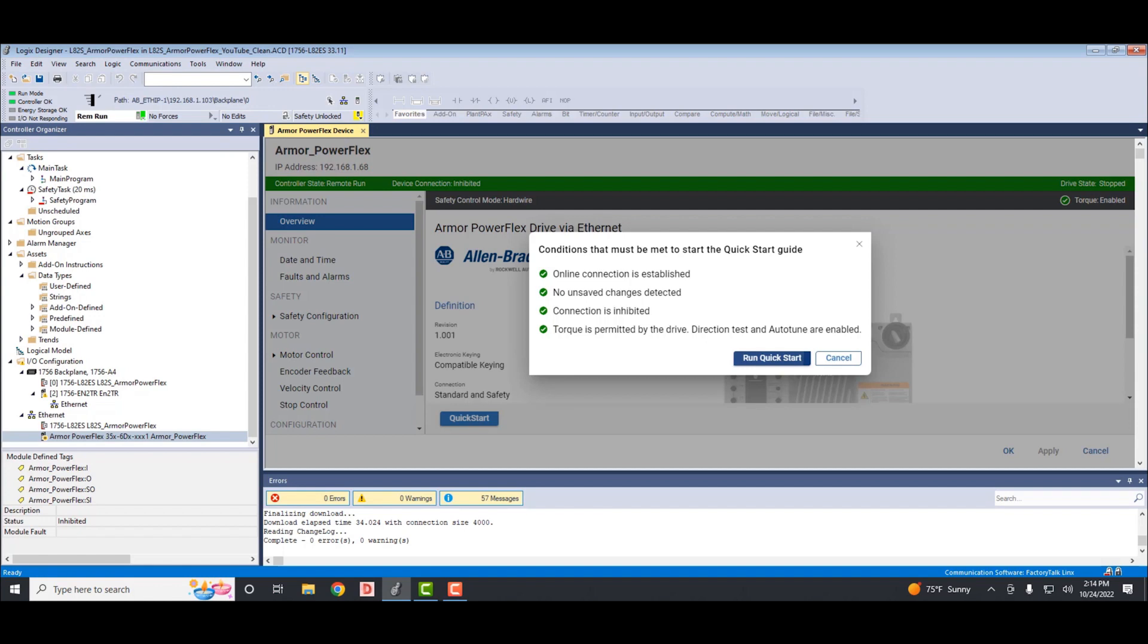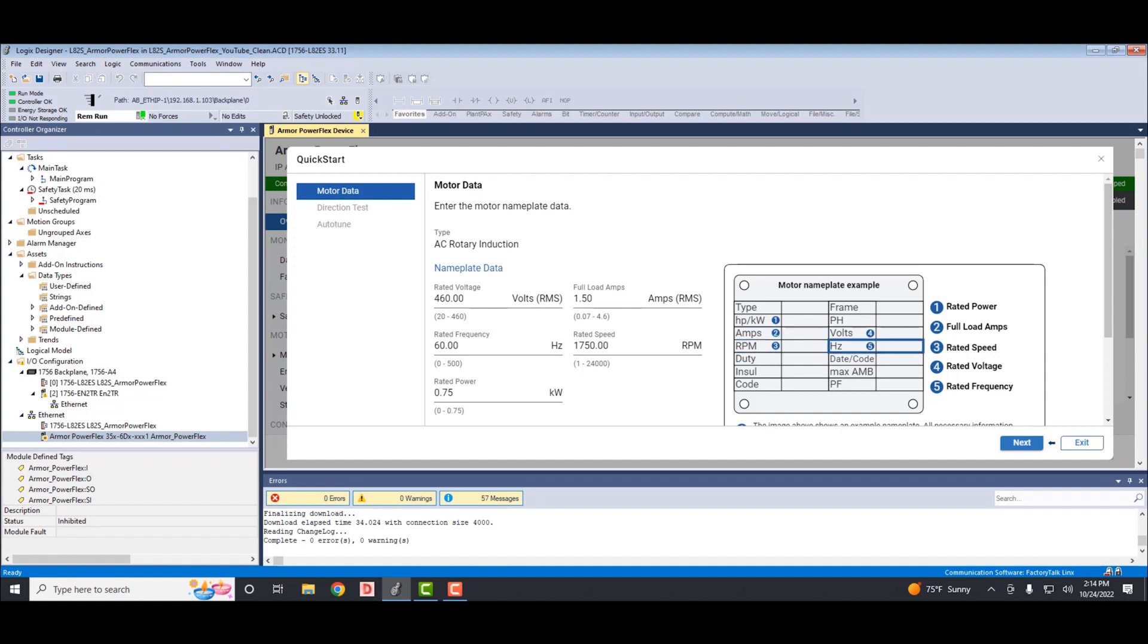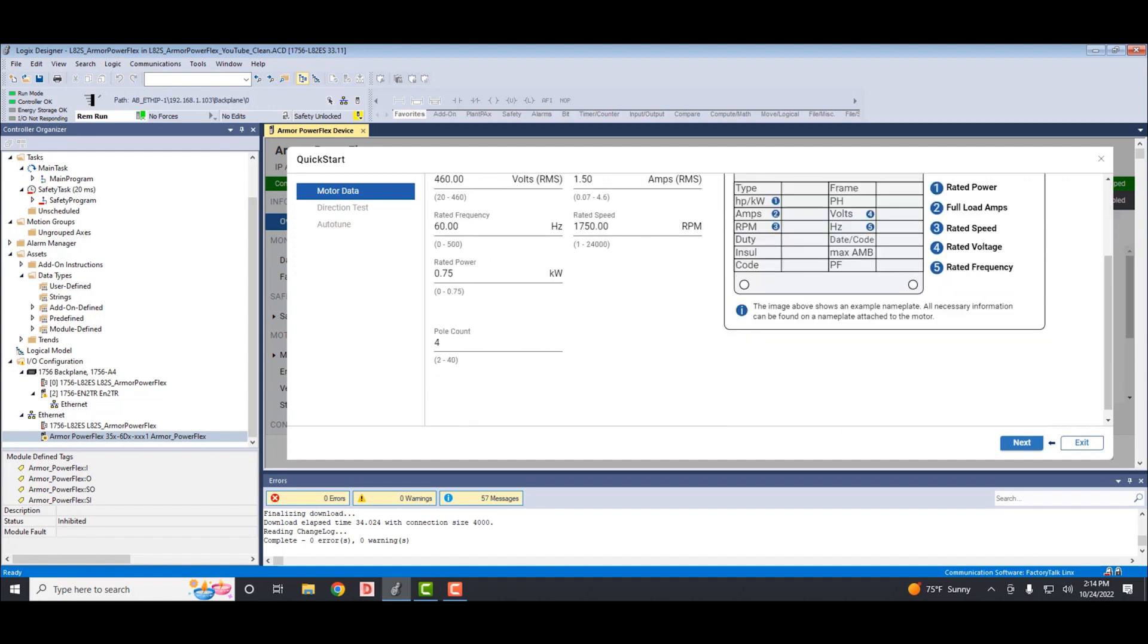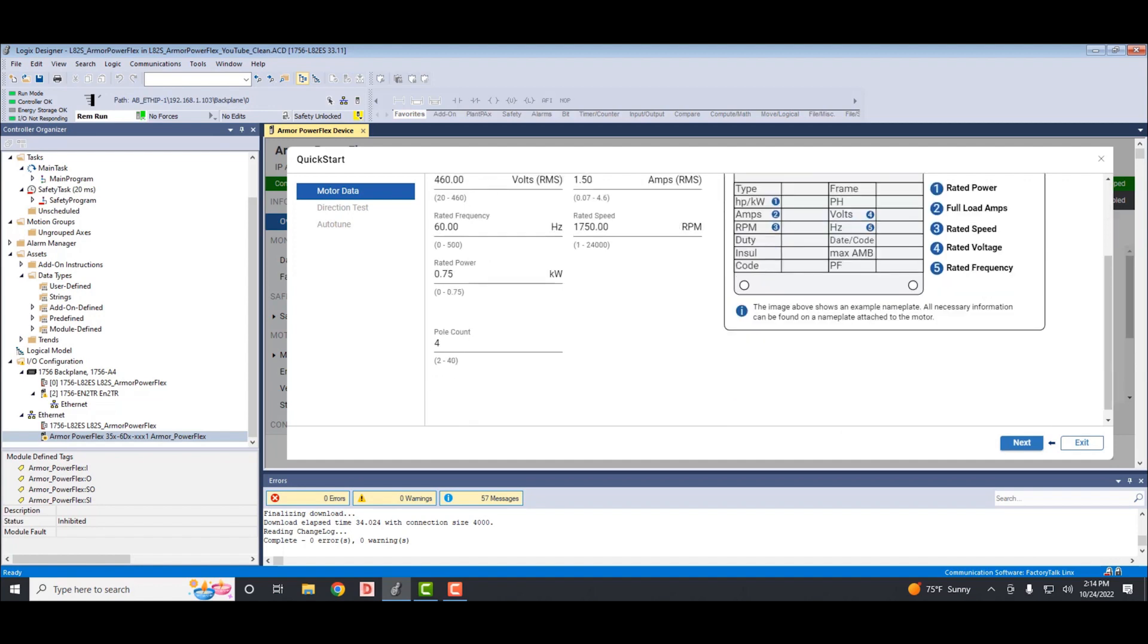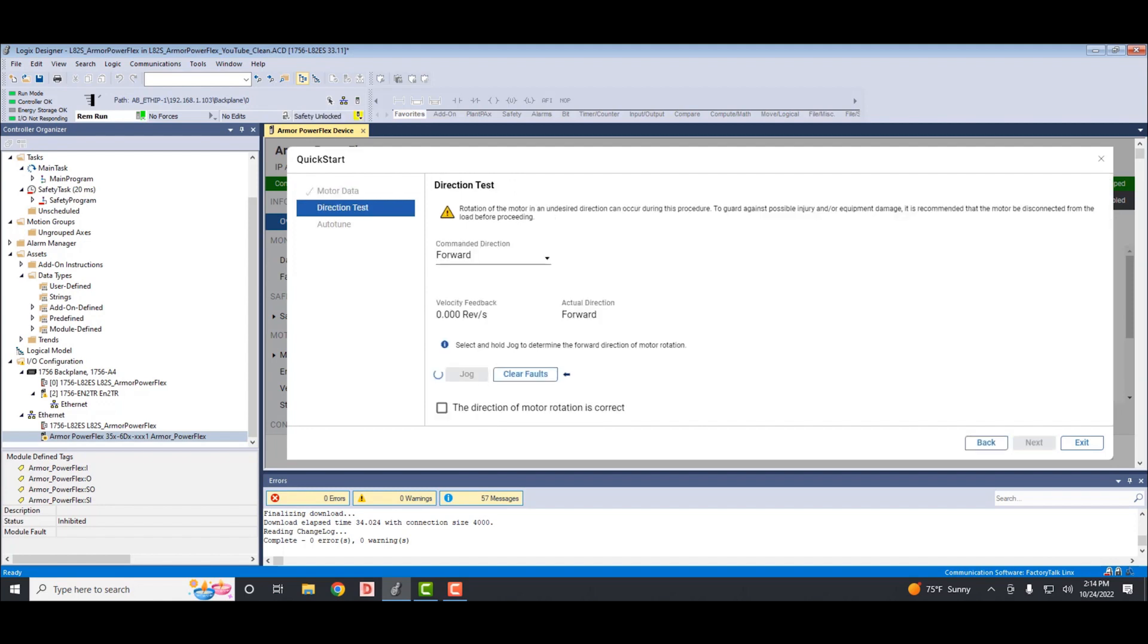The next step is where you can set up your motor nameplate data. I don't have a motor plugged in on this project, so I'll leave everything default and select next. Now you can perform a rotation test. It's a default of 10 revs per second, so you can hit the jog button. You will see the velocity feedback ramping up to 10 revs per second. Once you let go of the button, you'll see the velocity feedback ramp down to zero.